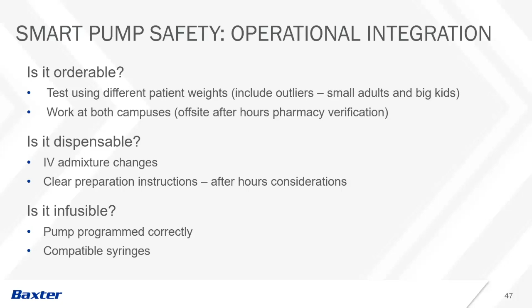We promoted compatible syringe use throughout our organization. Addressing compatible syringe selection within the pharmacy was accomplished by collaborating with our pharmacy operational leaders and buyers. We utilized the EMR to address compounding with compatible syringes. Much more challenging is assuring the areas outside of pharmacy, the patient care units and the operating rooms, are stocked with compatible syringes.